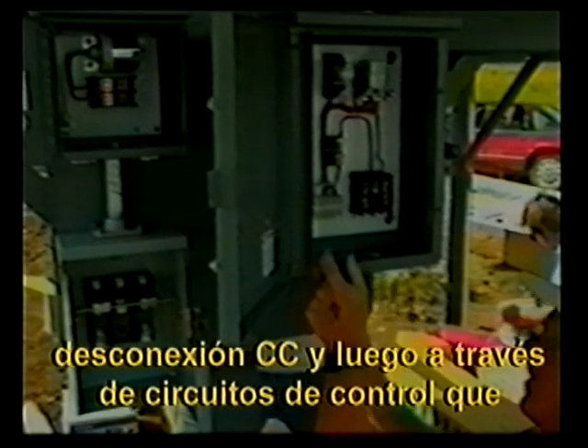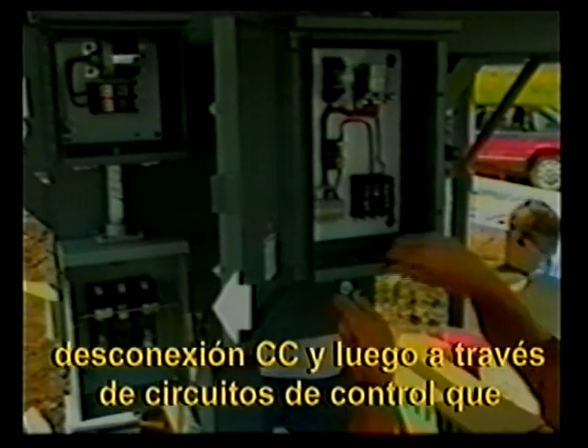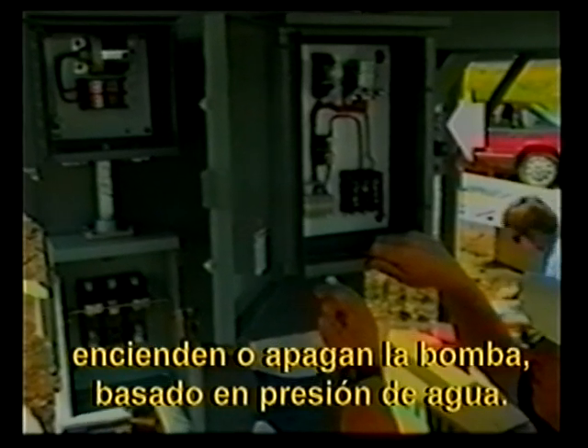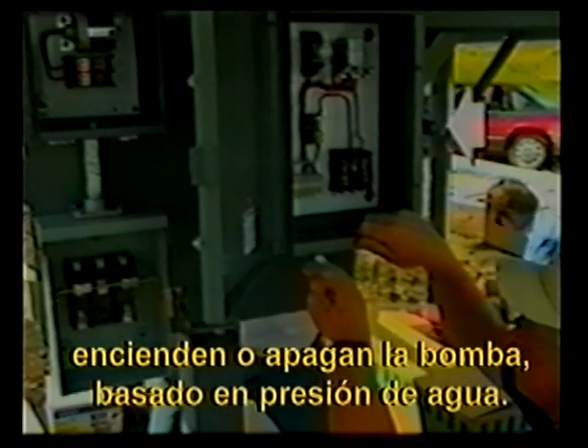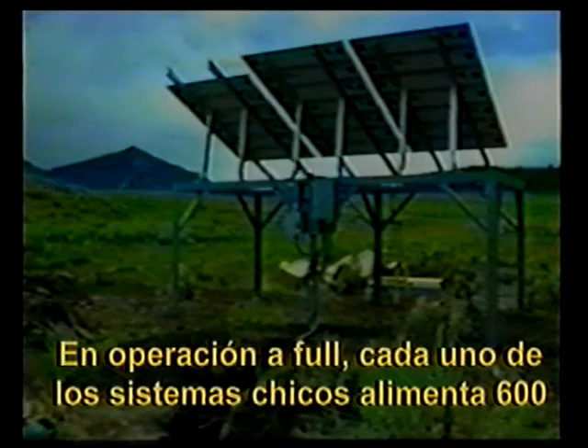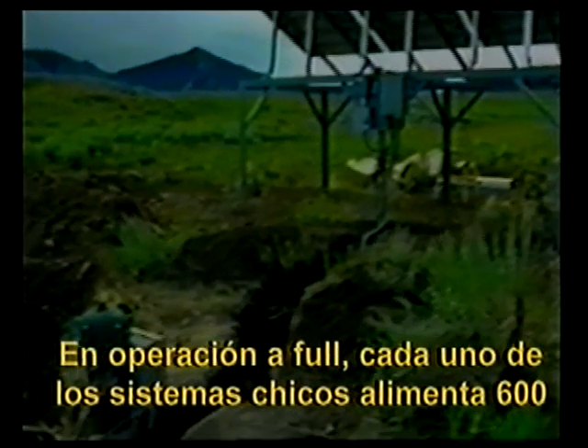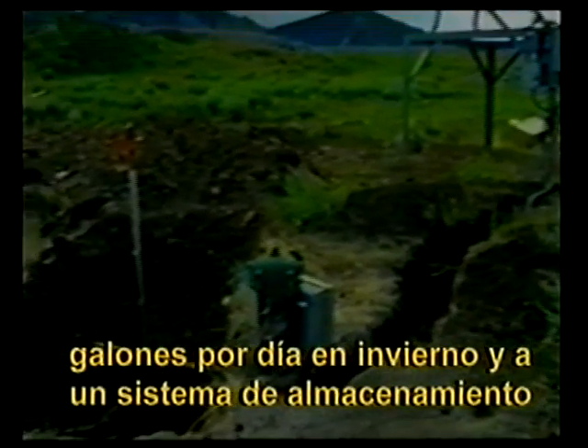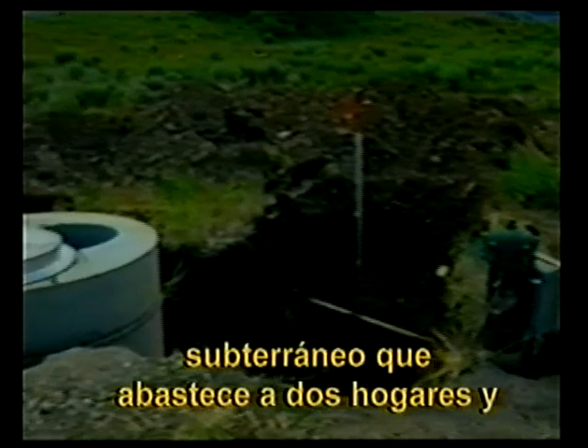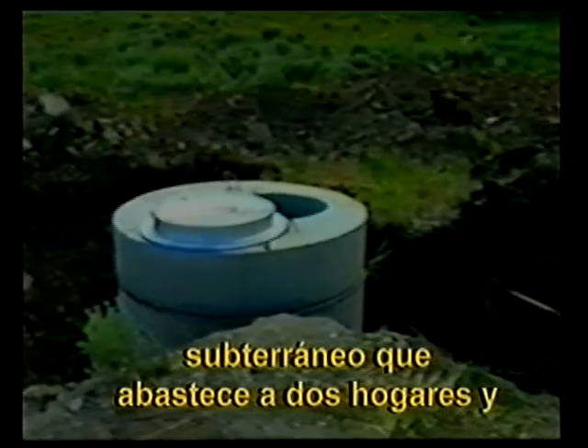The panel output is routed through a surge arrestor for lightning protection, through the DC-rated disconnect switch, and then through control circuitry that turns the pump on or off based on water pressure. When fully operational, each of the 2 small systems will feed 600 gallons per day in winter into an underground storage system that will serve 2 home sites and 2 guest homes.